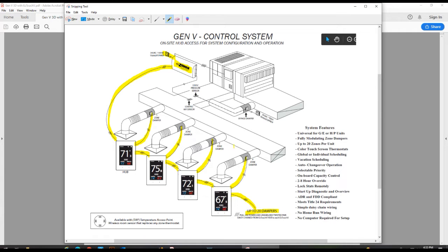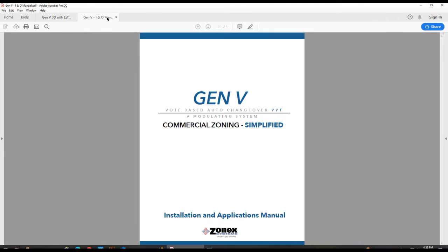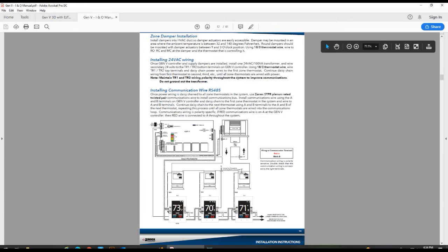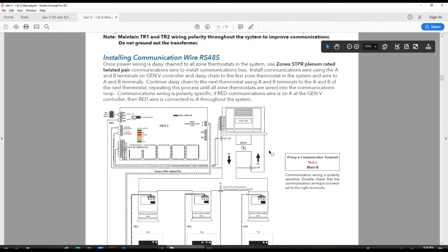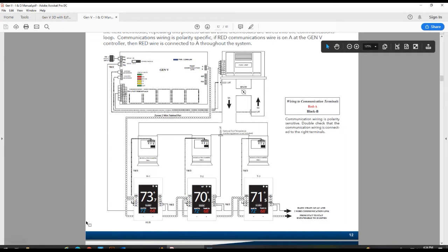The Gen V controller comes with several sensors, a leaving and return air sensor, and you'll want to install those appropriately. And then the controller also wires into the rooftop unit or split system that it is controlling. We're going to dive down into a little more detail on the wiring of the Gen V controller. So let's go ahead and switch over to our manual, which you should have received with your Gen V control system. In the instructions we give a detailed description of how to wire the Gen V controller to each thermostat, so we'll cover that here in more detail.